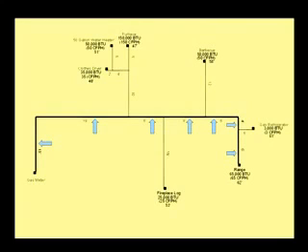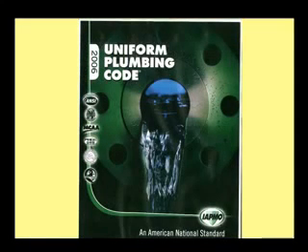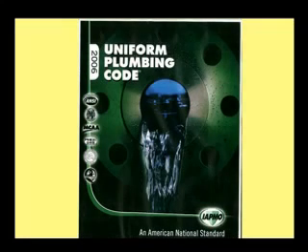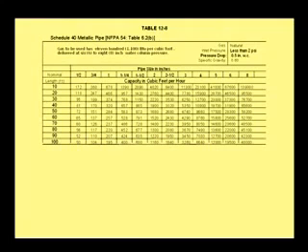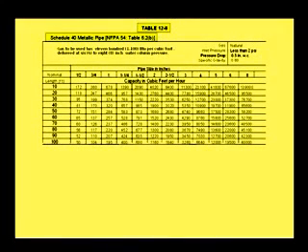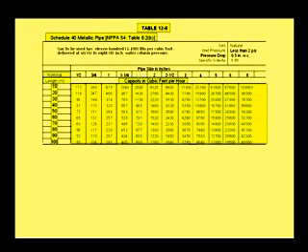All of these sections total 62 feet. We will be using table 12-8 from the 2006 Uniform Plumbing Code. Notice in the code book there are several tables. The main difference is in the type of pipe that can be used, ranging from polyethylene to stainless steel. In this sizing example, we will use the most common one — table 12-8 for schedule 40 metallic pipe. The length of run is noted in the left column; find the demand in cubic feet per hour to the right in the columns, looking up to find the nominal pipe size required in the top row.